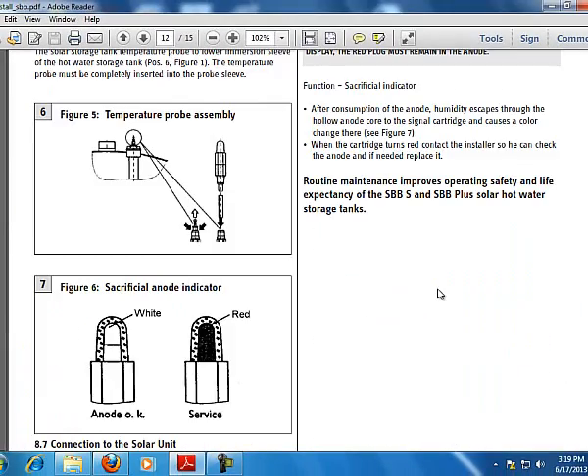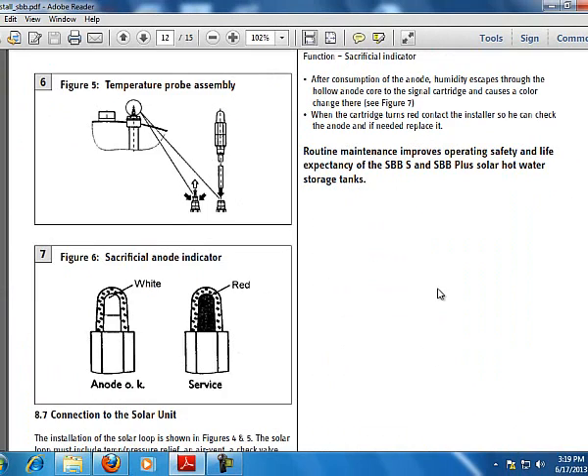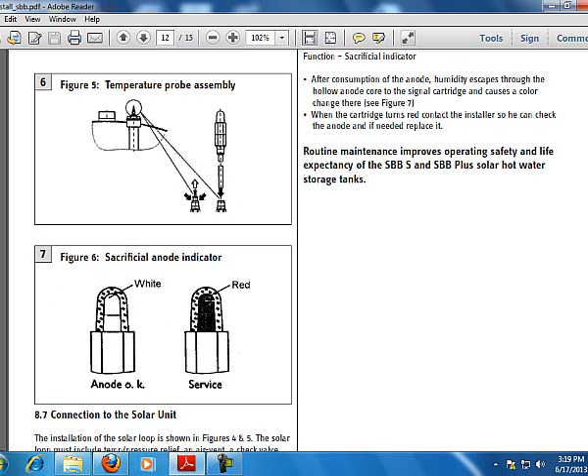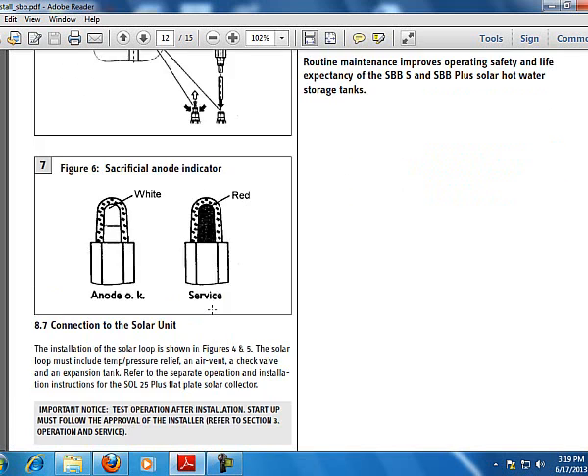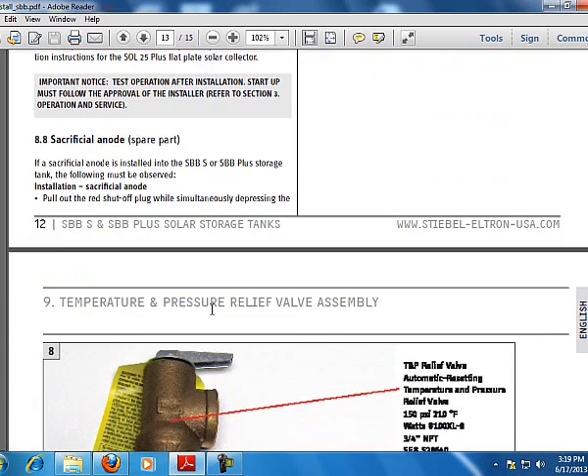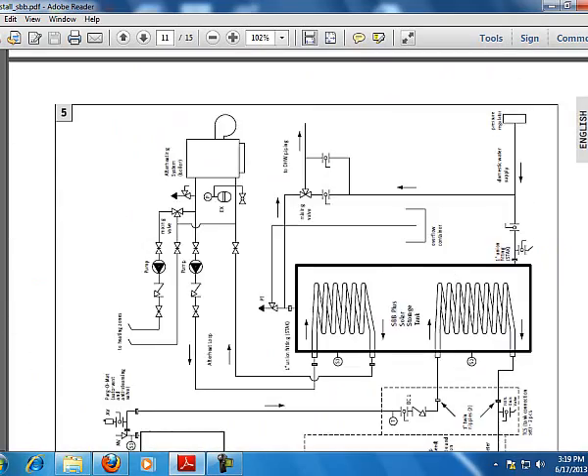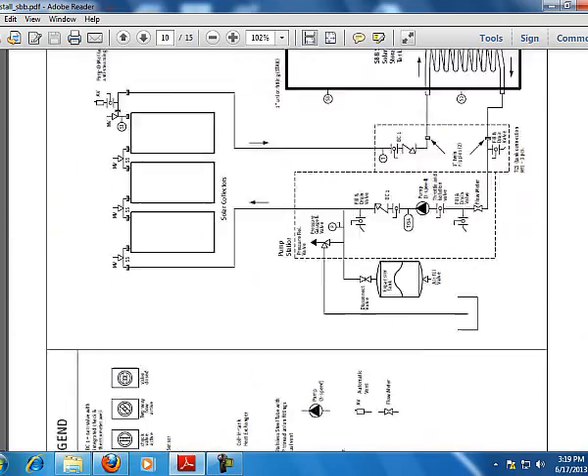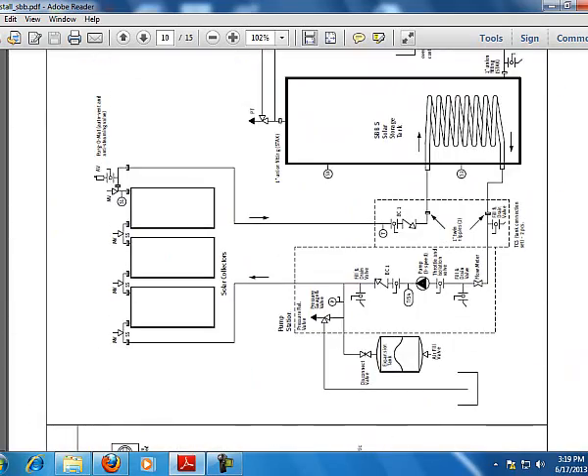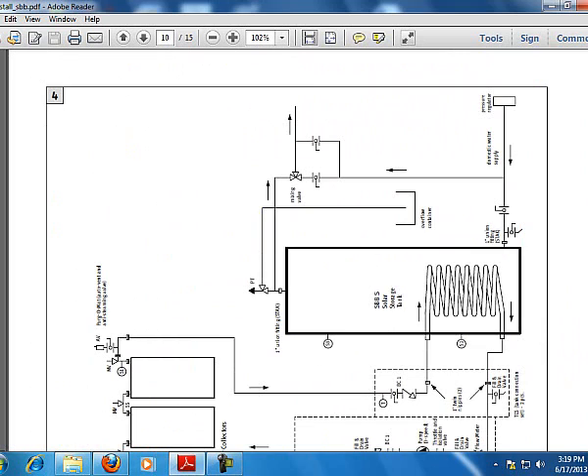A couple things. Every closed pressurized tank system will have to have a sacrificial anode. The best anode that you could use is a magnesium insertable rod or aluminum. That would be your next best. So on the sacrificial anode, when you look inside of it, you'll see that if it's white, it's okay. As that wears out, you'll start to see that inner connection start to turn red on you, and that's time to replace that. Let me go back up here and talk about a few other things that we have to have in common with this.